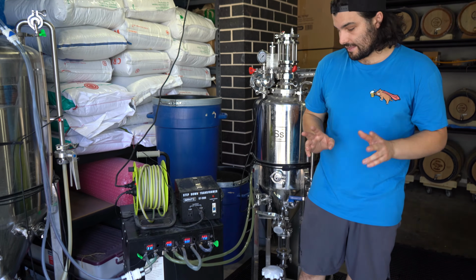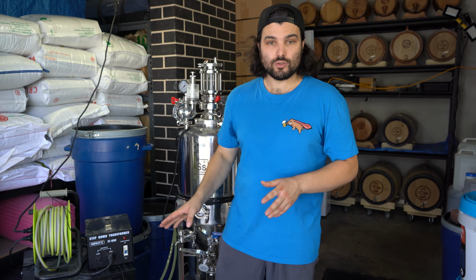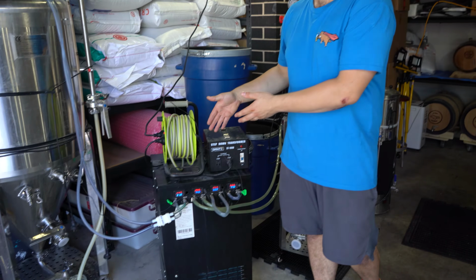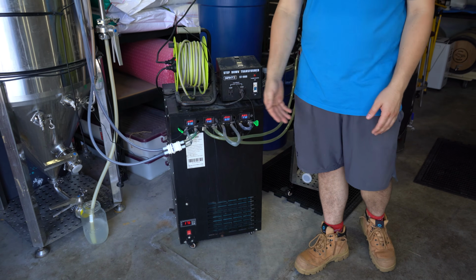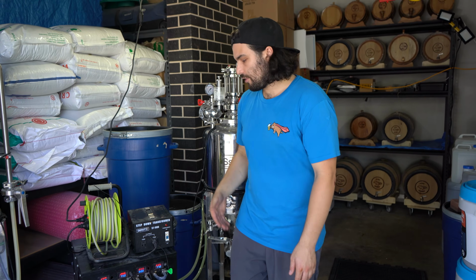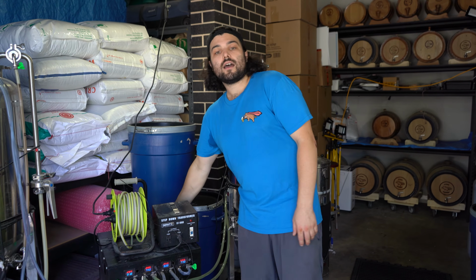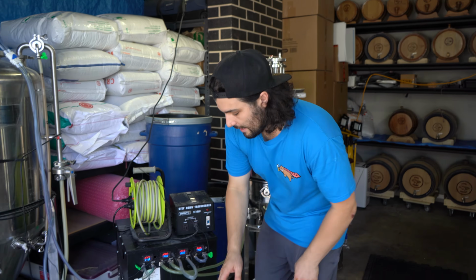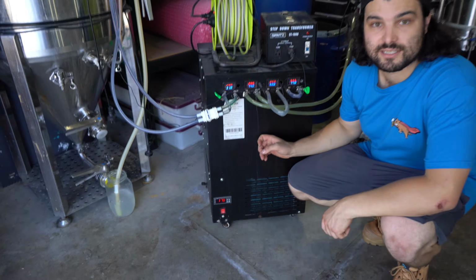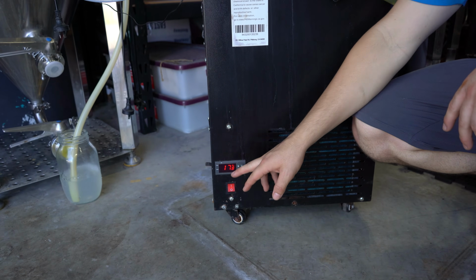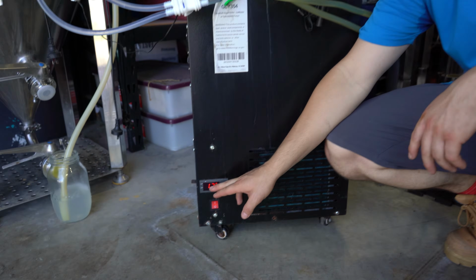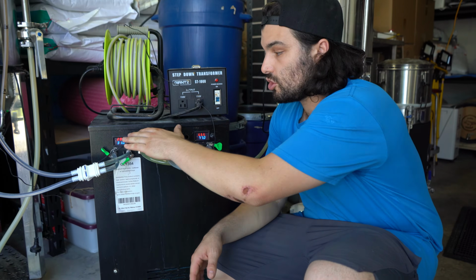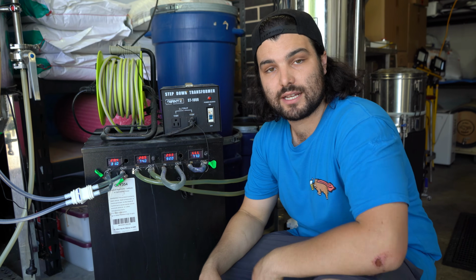Next big pro is that this thing is ridiculously user-friendly. All there is to it is you fill this thing up with your glycol liquid, so your 20% glycol, 80% water, 30 liters total inside the tank. After that, all you need to do is set a temperature for the reservoir itself. So if you're controlling multiple vessels, you could set this thing to be -2 degrees Celsius, and then you just choose what temperature you want your different vessels to stay at.